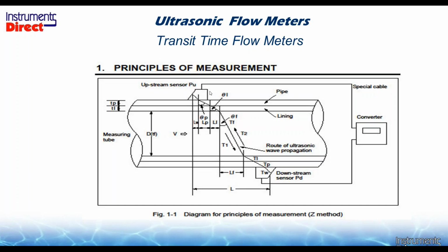So they have a piezoelectric crystal inside here that they energize, which sends a sound burst through a pipe wall. Well, we need to know what the sound speed of, say, this carbon steel or ductile iron pipe is. And then say we had a liner, a Teflon liner or a mortar lining, we need to know the sound speed of that.